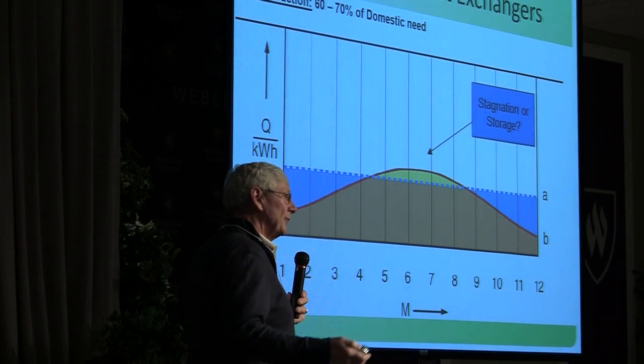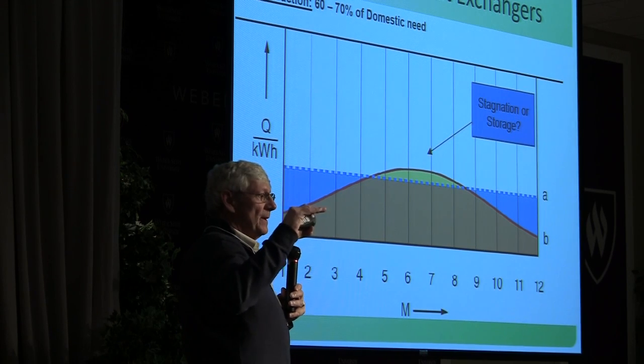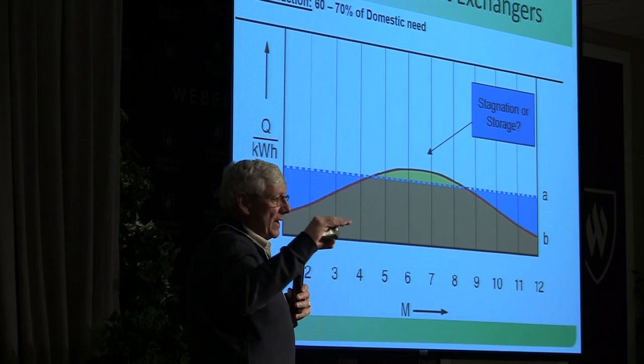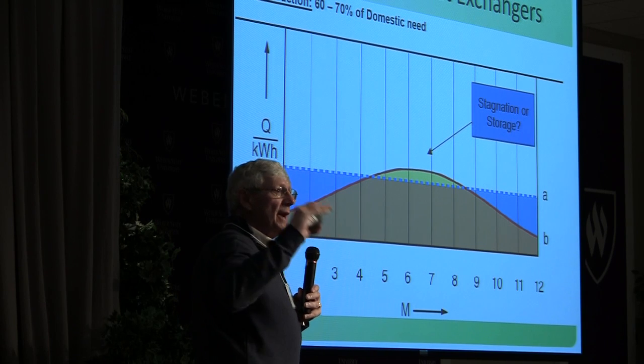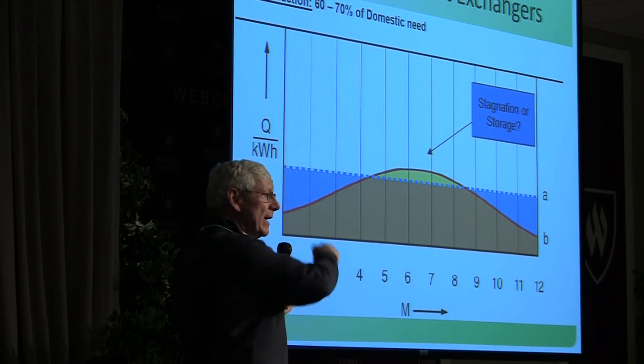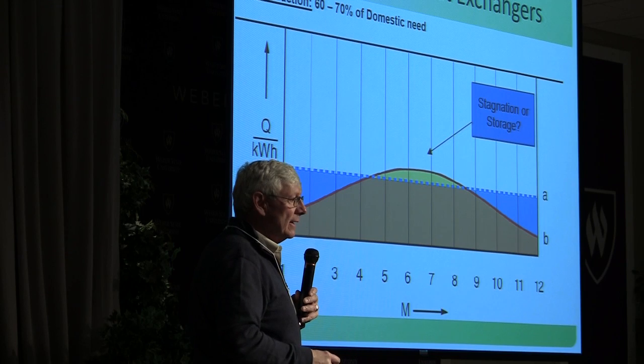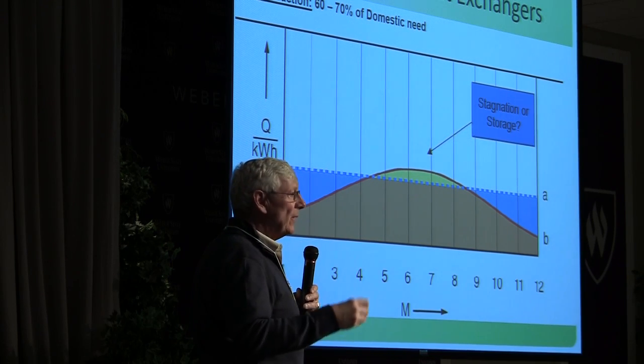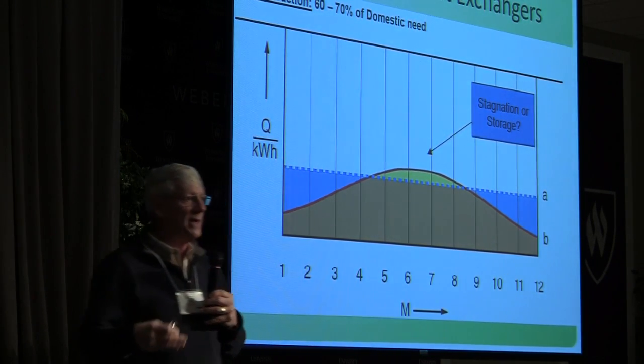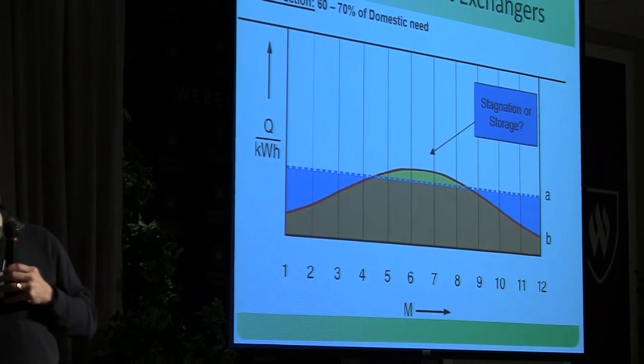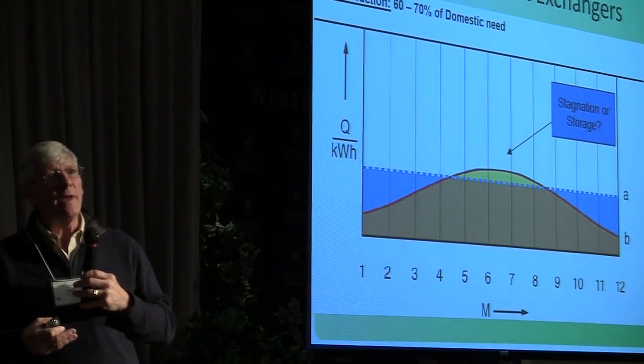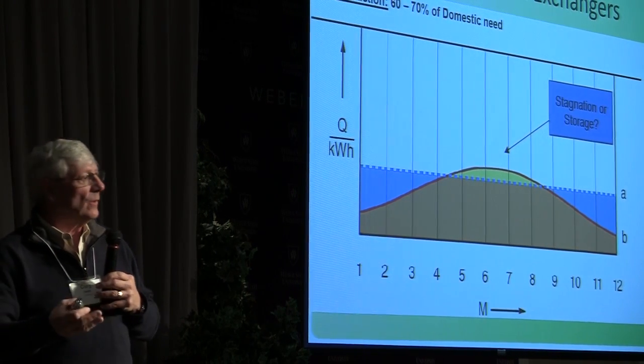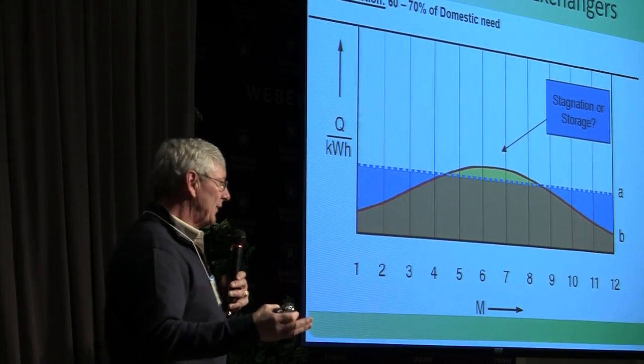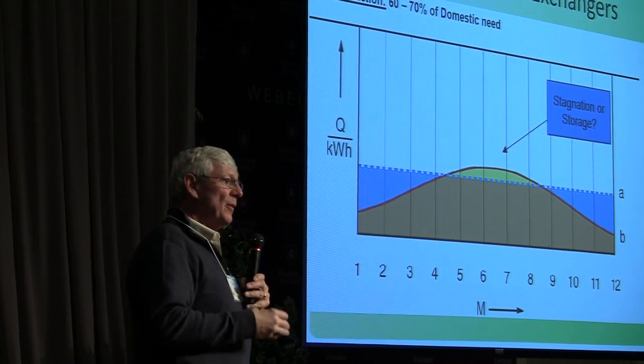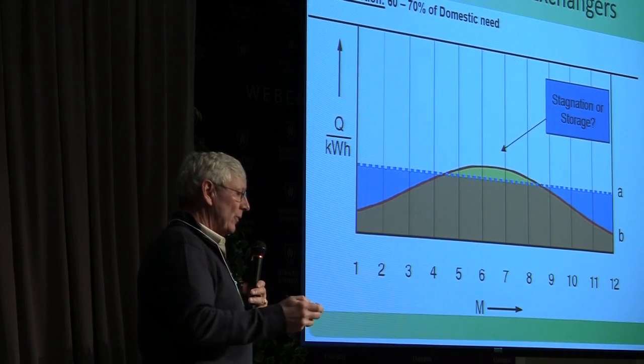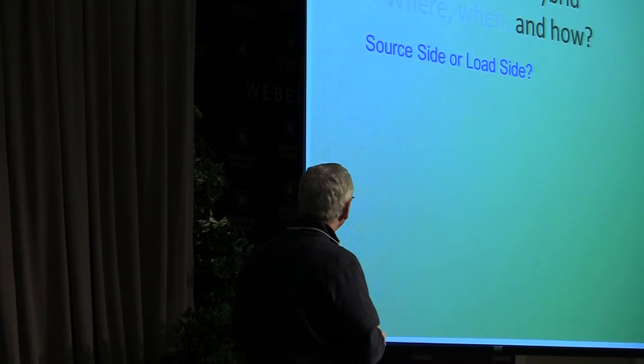And this works best in the shoulder months. Don't think of it just in the summer where you get this stagnation curve. On a weekend in a school, you have the same curve, but it may come up in the middle of the day in January. We have buildings we're watching on these systems day-to-day where the temperature on the solar ground source combination system is 61 degrees, where normally it would be somewhere around 45. So we've got much more energy available.